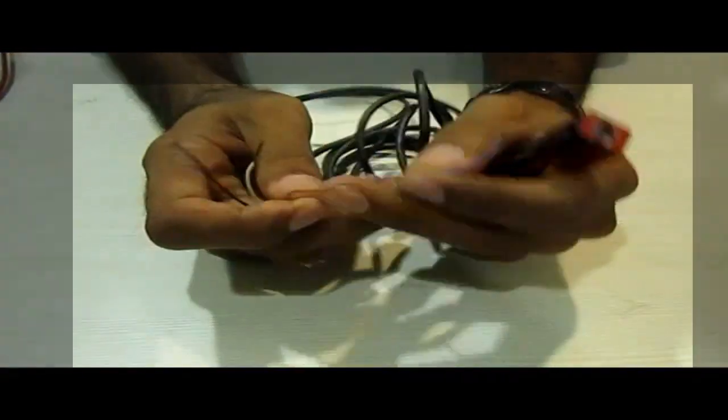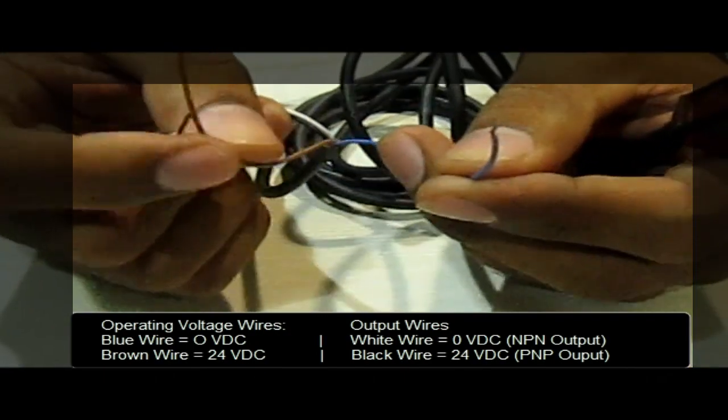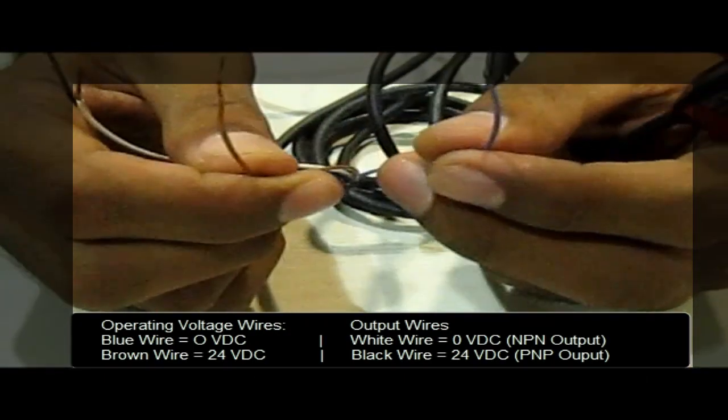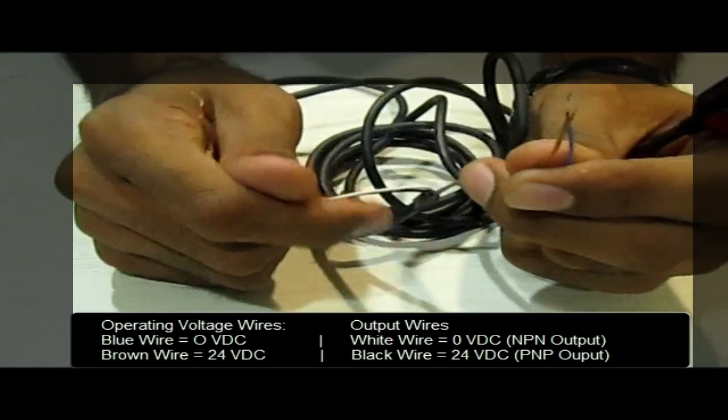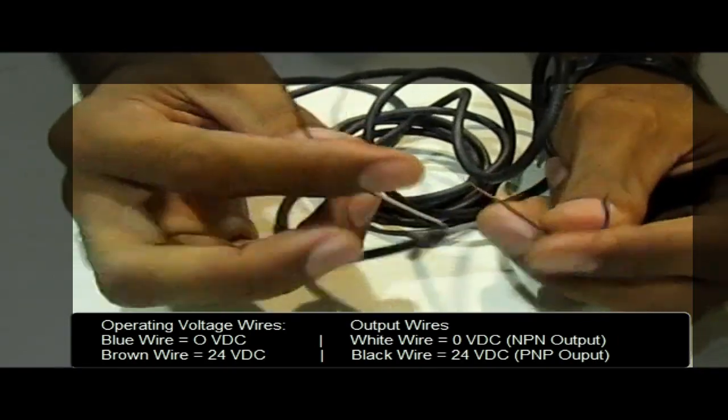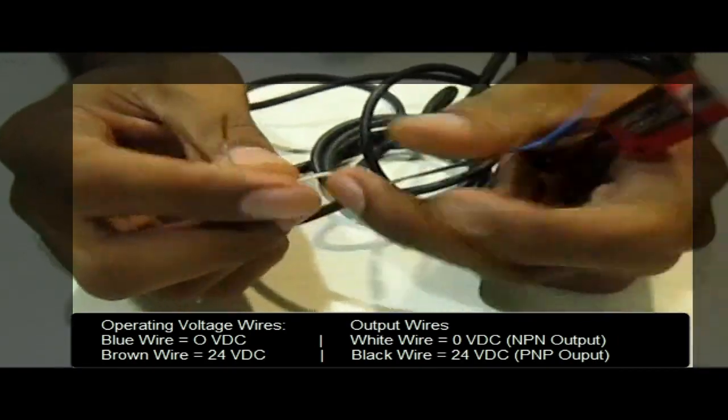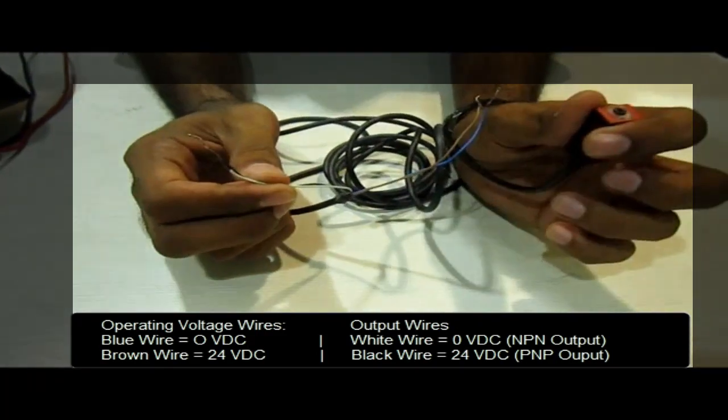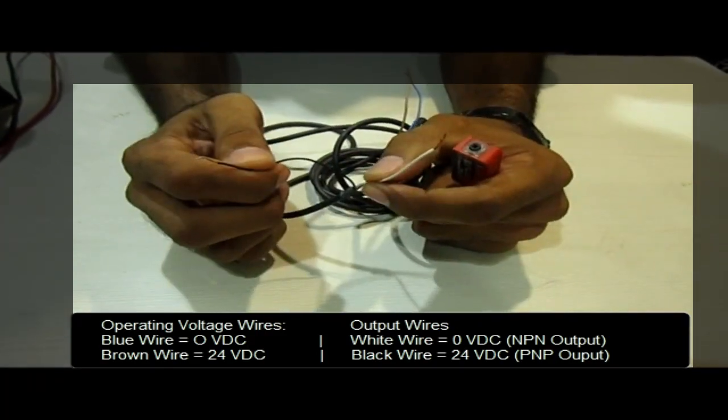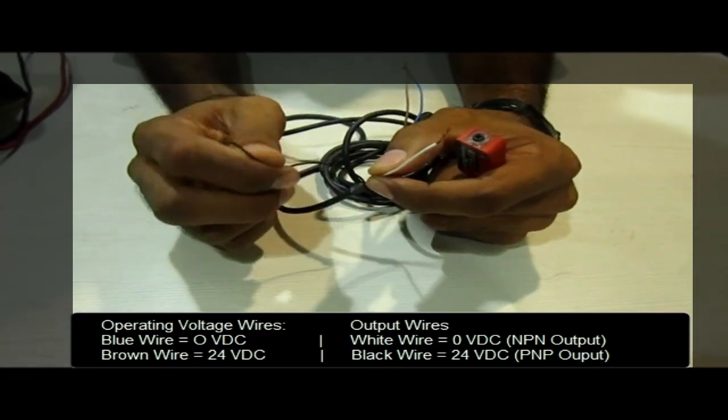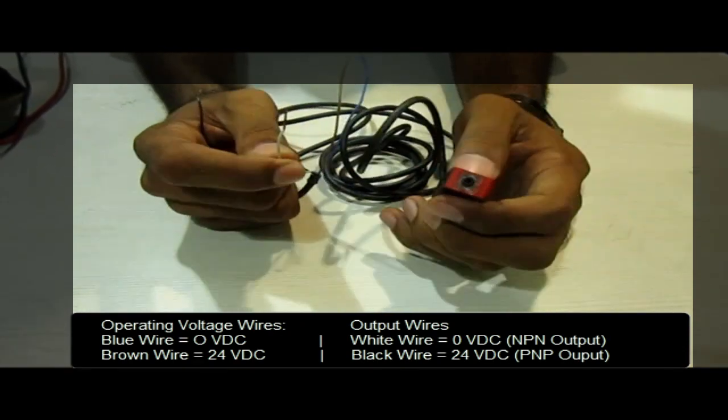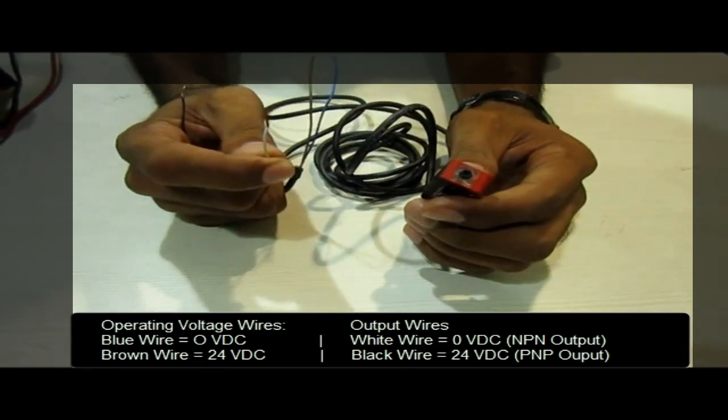As you see closely this blue wire is given 0 volt, this brown wire is given 24 volt. These are the operating voltages which will turn on the sensor. These two wires are the output wires. When the sensor detects any object this black wire will give 24 output which means it gives PNP output and this white wire will give 0 output which means it gives NPN output.